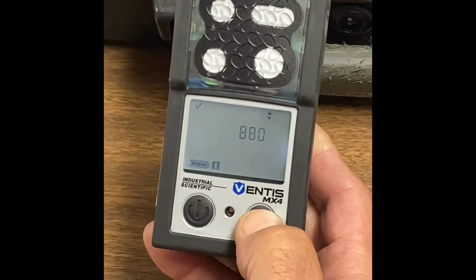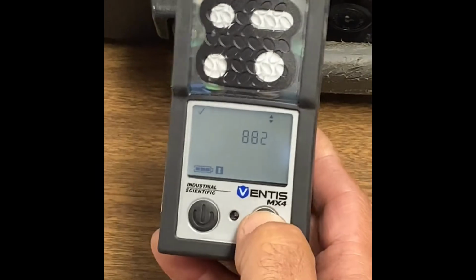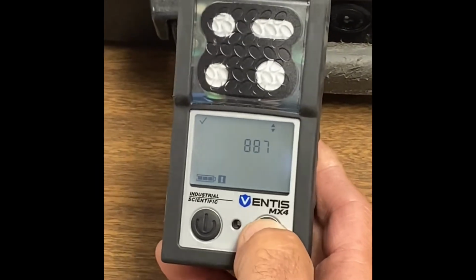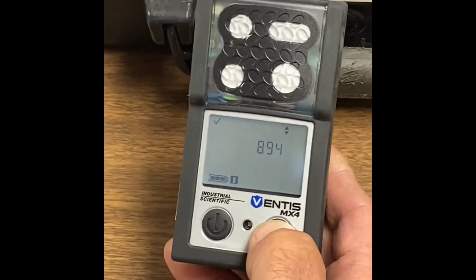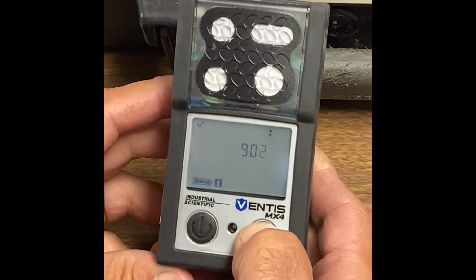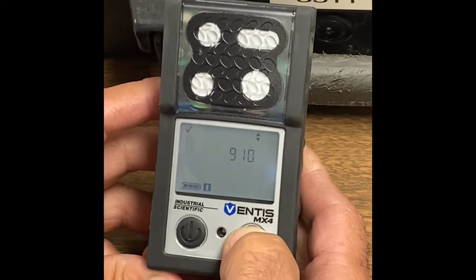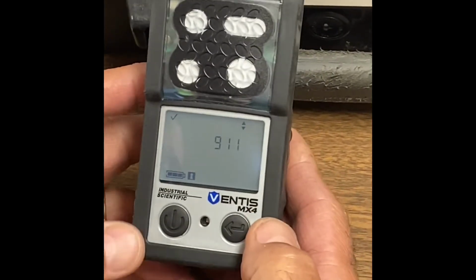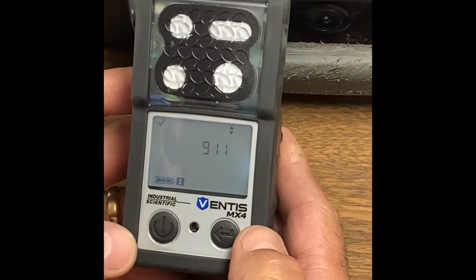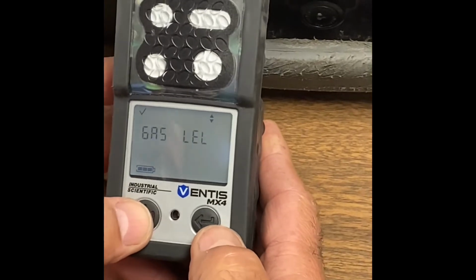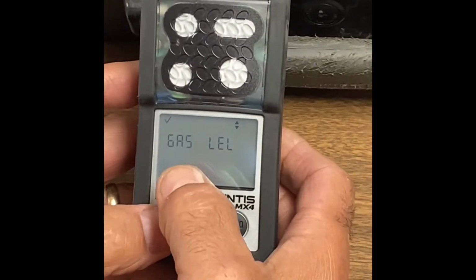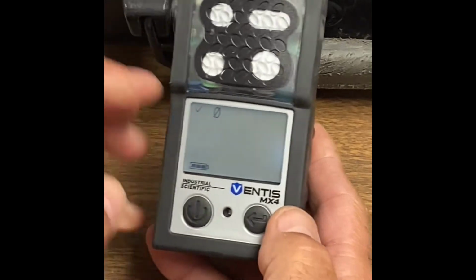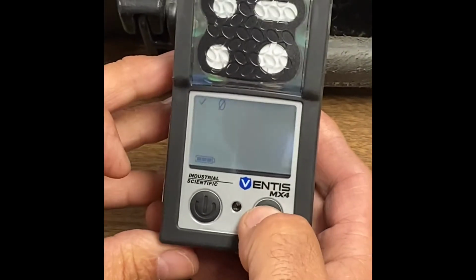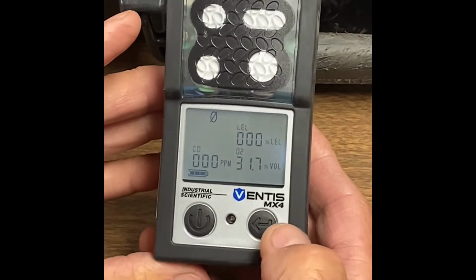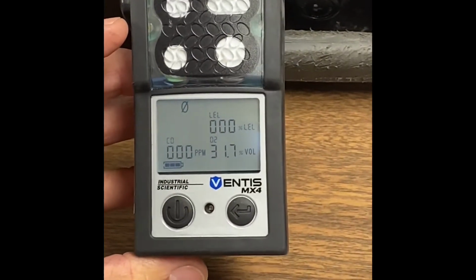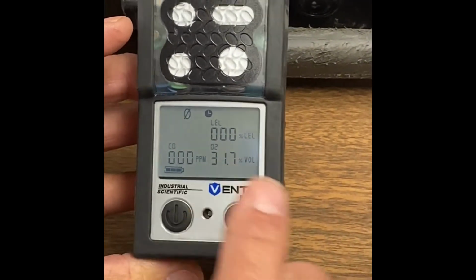So I'm going to stop. I just stopped at 880, and then I individually scroll up one number at a time until I get to 911. So now I'm at 911. I want to go ahead and press the enter button. And you should see, the first time you press, gas LEL, and then the next one is 0. Go ahead and press the enter button, and you'll see it's the same as doing a bump test, zeroing the unit.